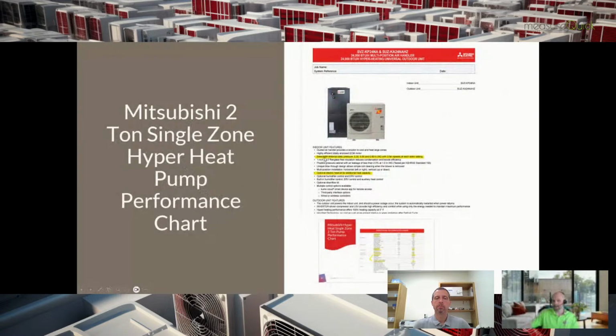First off, this particular air handler has a selectable external static pressure of 0.3, 0.5, or 0.8 with 3 fan speeds to go with it. So guys, we can get down to some pretty low BTU equipment and still push the air around the way we need if we pay attention to the air handlers here. Like all these inverter heat pumps have various air handlers that can be matched up with them. Some have the static pressure, or the muscle behind them, to push the air where we need it to go, and allow us to do some pretty cool designs with our ducted systems and still get the air where we need it. And then some of them are not going to do that without very close attention to your duct design. So just be aware of which air handler you're matching these up with.